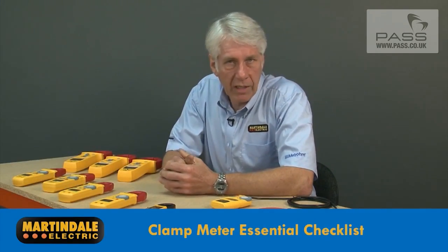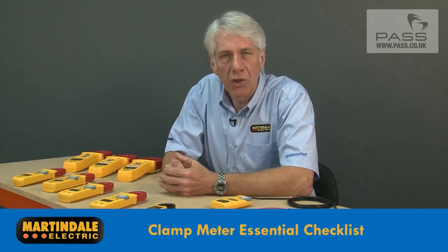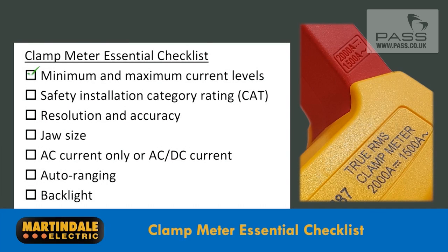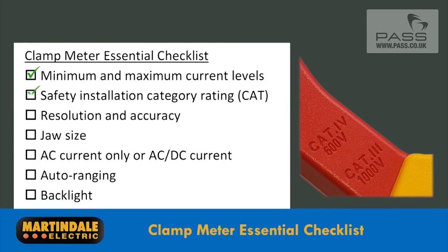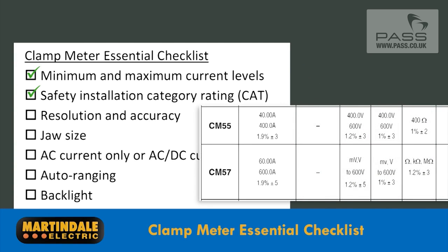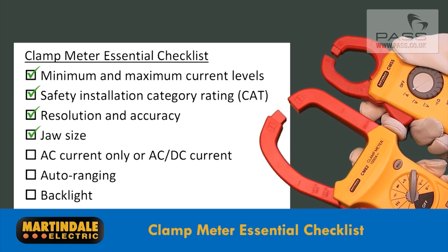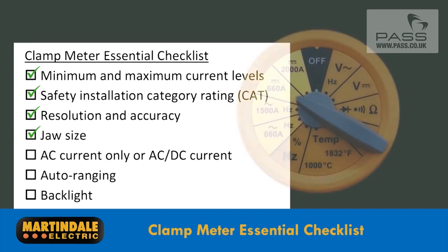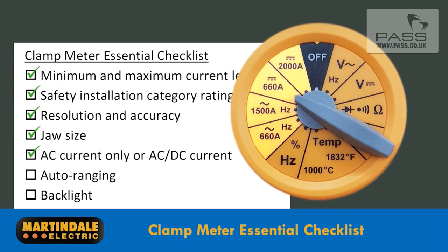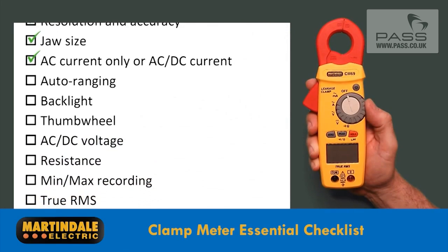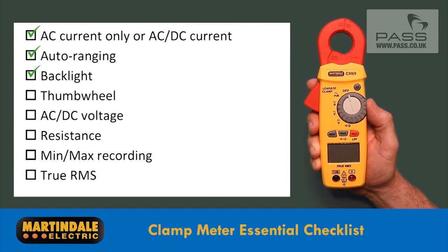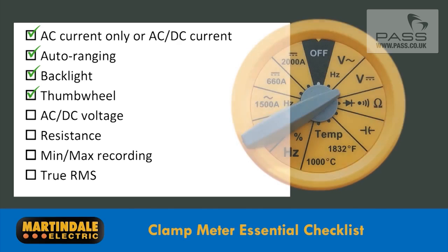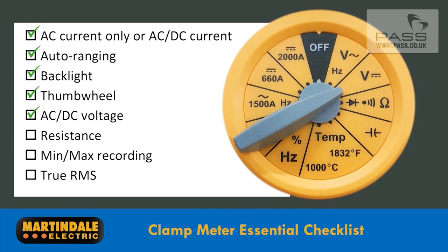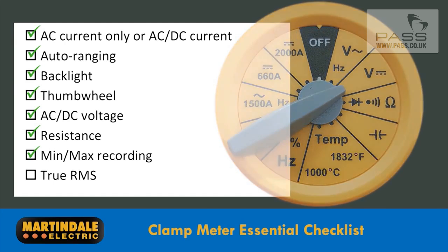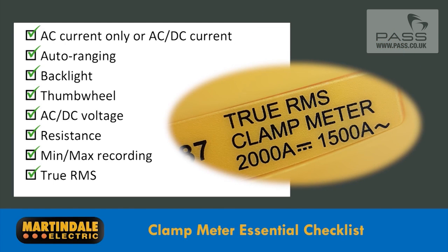To help choose the right product in your category of clamp meter, here is the essential checklist. The minimum and maximum current levels, the safety installation category rating for your application, the resolution and accuracy to accurately measure the minimum level of current, jaw size for access and maximum conductor size, AC only current or AC and DC current, ease of use including features such as auto ranging, backlight and thumb wheel for function select, any additional functionality including AC-DC voltage, resistance and min-max recording, and True RMS measurement.